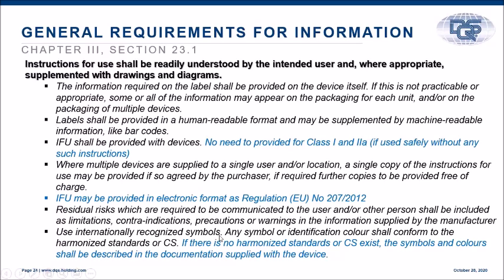So, use of internationally recognized symbols. Any symbol or identification color shall conform to harmonized standards or common specifications. If no harmonized standards or common specifications exist, you can define them. The symbols and colors shall be described in the documentation supplied with the device.